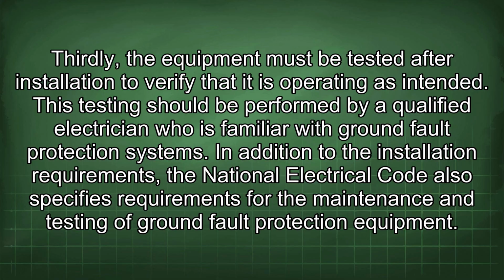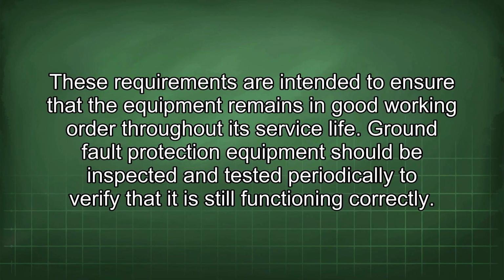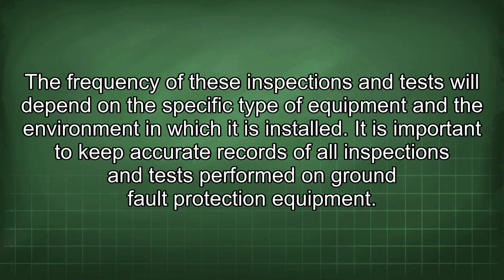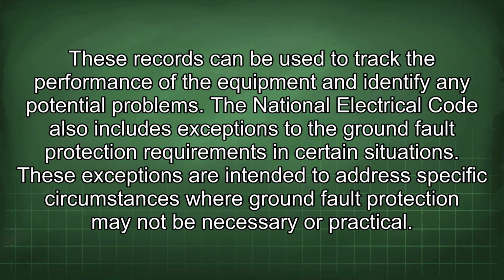In addition to the installation requirements, the National Electrical Code also specifies requirements for the maintenance and testing of ground fault protection equipment. These requirements are intended to ensure that the equipment remains in good working order throughout its service life. Ground fault protection equipment should be inspected and tested periodically to verify that it is still functioning correctly. The frequency of these inspections and tests will depend on the specific type of equipment and the environment in which it is installed. It is important to keep accurate records of all inspections and tests performed on ground fault protection equipment. These records can be used to track the performance of the equipment and identify any potential problems.